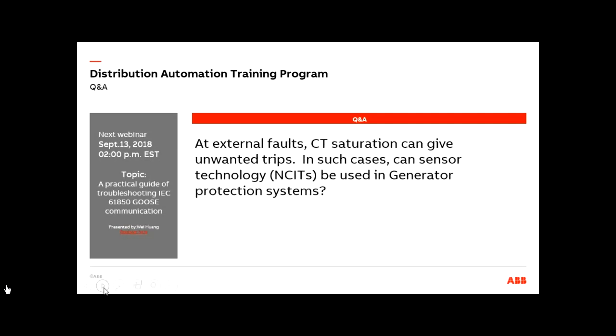Last question for today. At external faults, CT saturation can give unwanted trips. In such cases, can sensor technology be used in generator protection systems? Absolutely. Sensor technology is the best way to go, because sensors are not affected by saturation. That is one benefit of having a sensor. A sensor has two advantages. One is that it does not have multiple ratios.